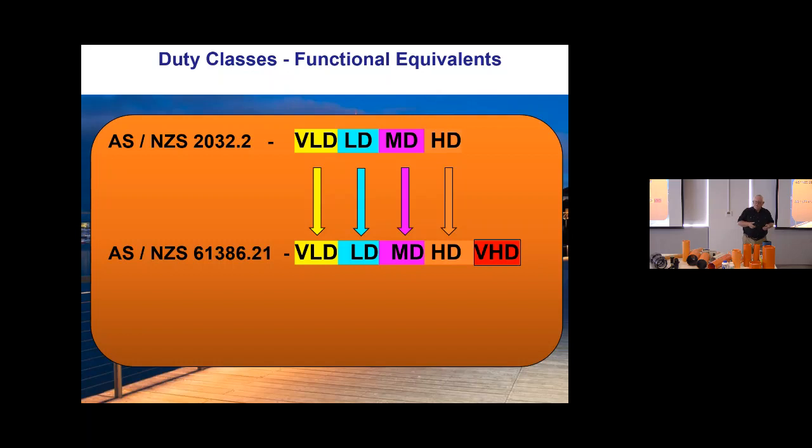The extra structural performance that you get out of VHD, which is SN25 versus SN10, really doesn't offer too much extra benefit unless the pipe is under very direct structural load, which you'd normally expect from traffic where the depth of cover is very shallow. The SN stiffnesses for the pipe, as I indicated on the previous slide, are known. And it's not too difficult, if you need to do the calculation, to relate the depth of cover and the amount of load that you're putting on the pipe using Timoshenko's relationship or something like that, and then just pick the pipe that's appropriate.